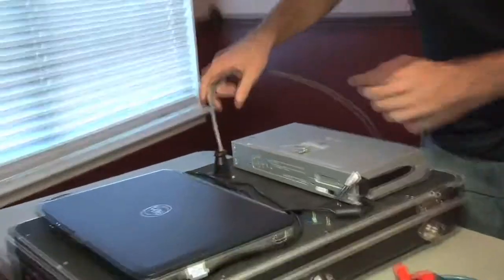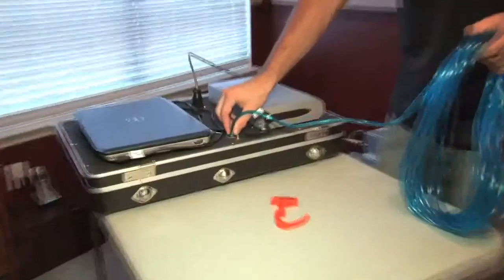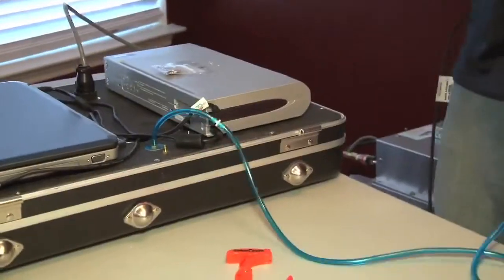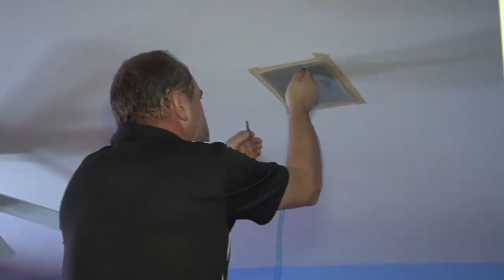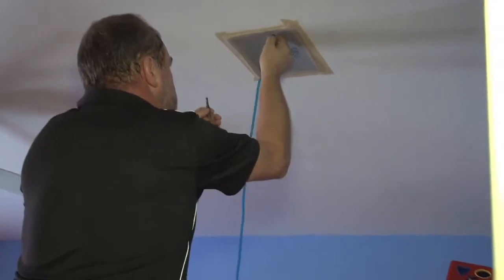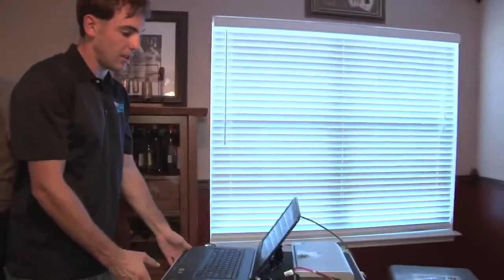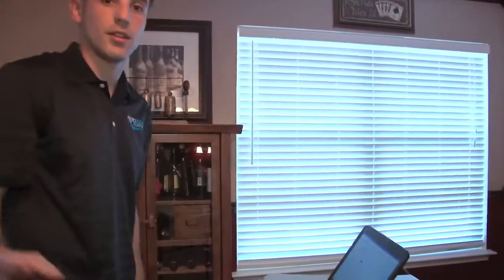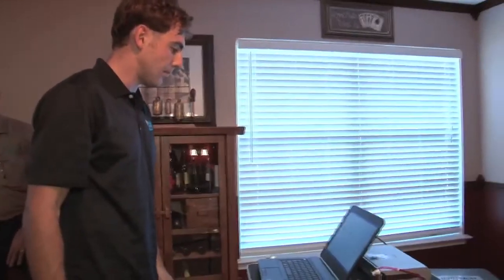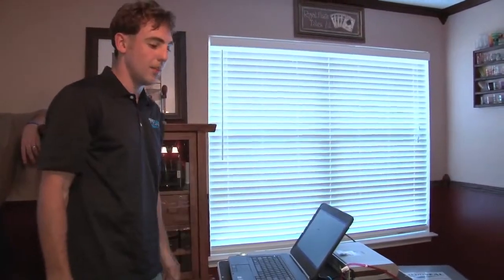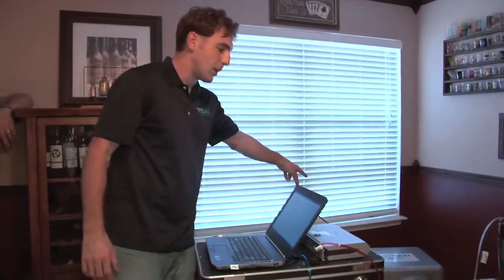We, by computer, determine what the leakage is before we put glue in, so that after we seal the system, we can then go back and see how much of an improvement we've made on the ductwork. This is the pre-sealing leakage test. Basically, we're pressurizing the system and finding out how much leakage there is, how many little holes there could be in the connections and in the ductwork and that sort of thing. We have a tube here that goes to the fans, so we know how hard the fan's working, and we have a tube here that goes into the duct system, so we know how much pressure is in the duct system. That's how we measure the amount of leakage.